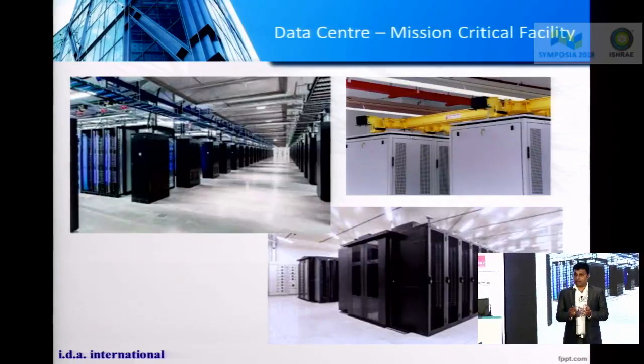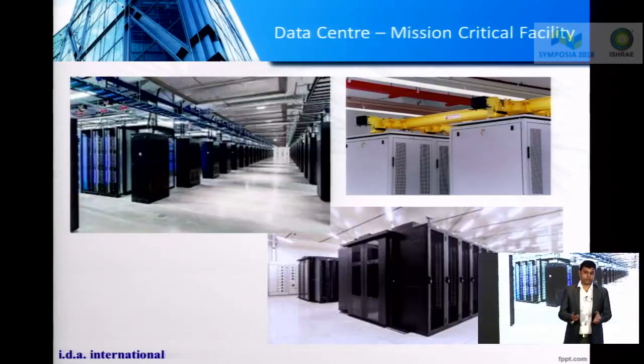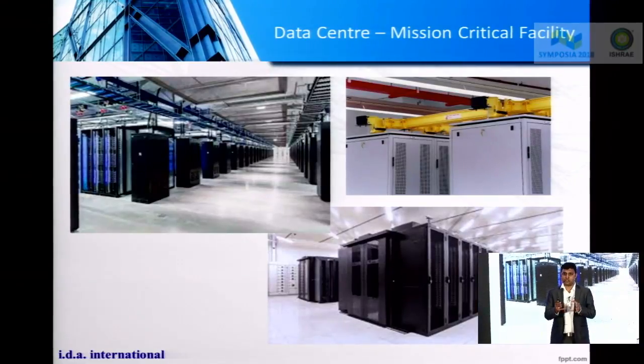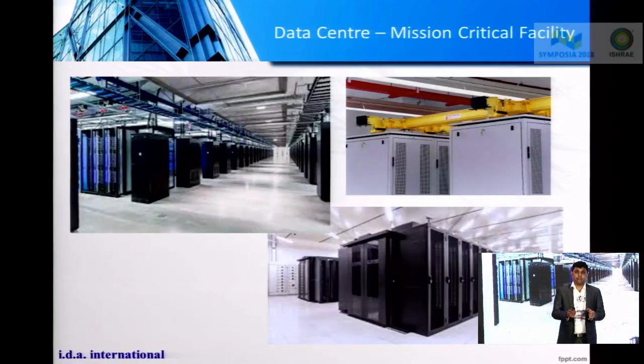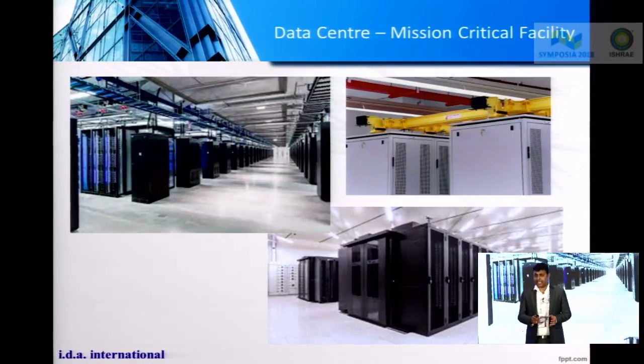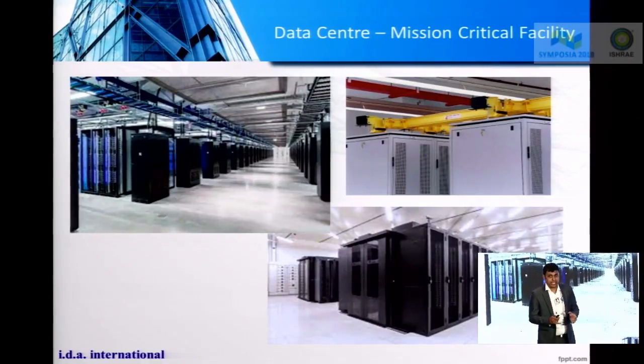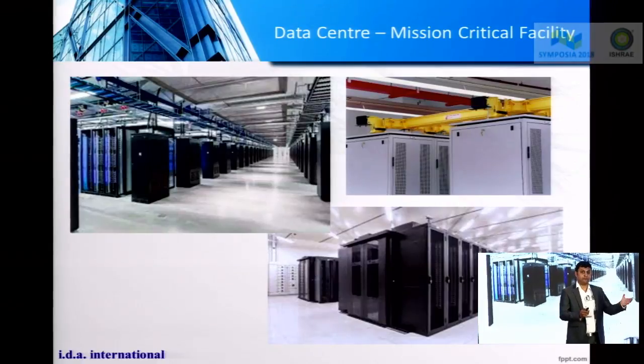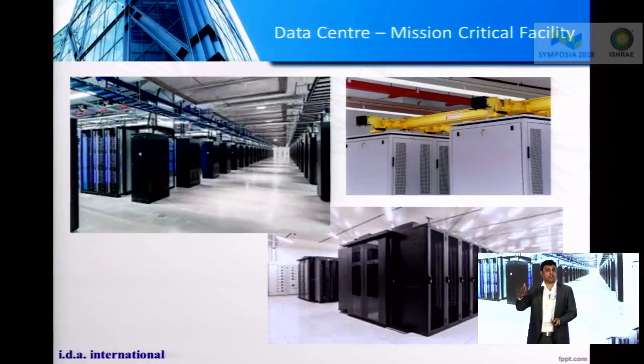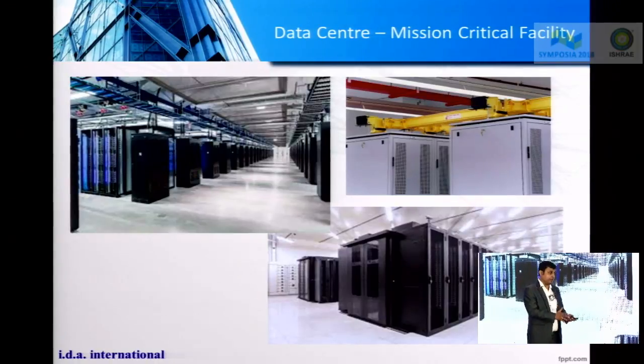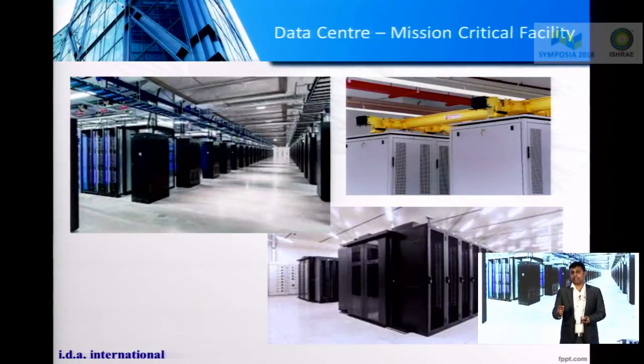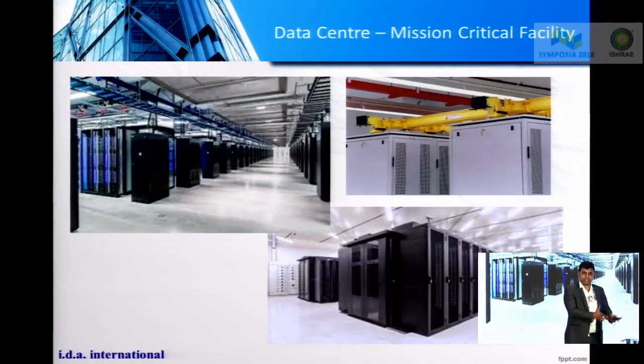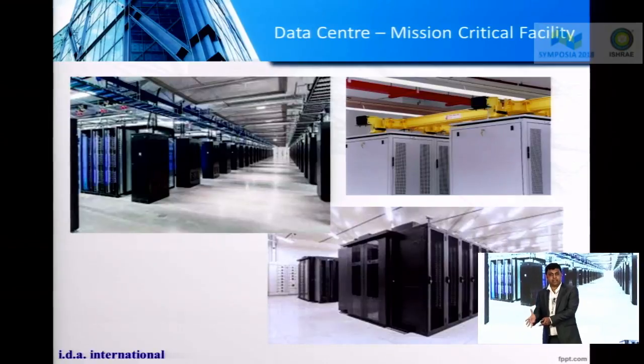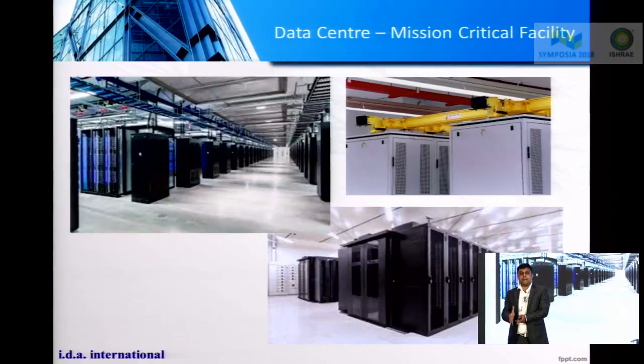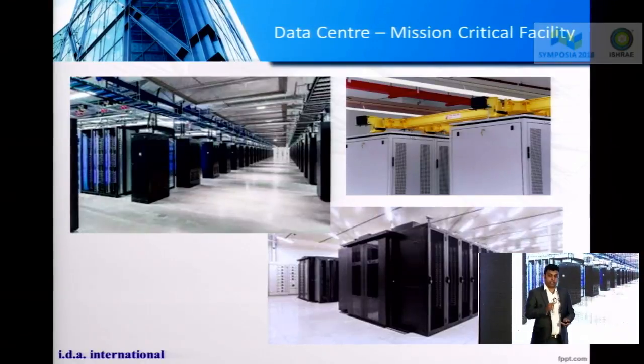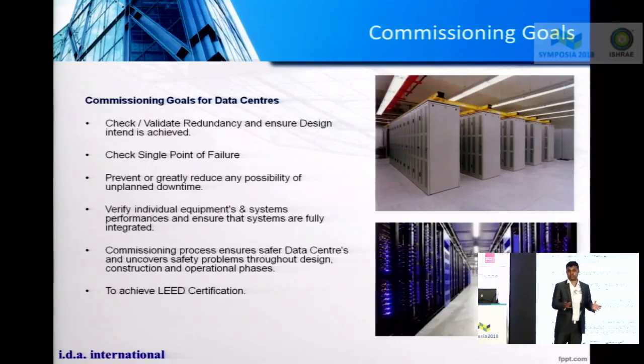Data center. There are many presenters who have told the importance of data centers, but we all know that a data center is a mission critical facility, which means a single failure could result in heavy economic losses. That's one of the reasons why many design consultants design data centers with tier 3 and tier 4, which means they're trying to add multiple layers of redundancy, which is pretty good. However, there's one thing that ensures that whatever you design is correctly implemented, correctly validated, correctly documented, operated, and maintained, and that's commissioning. So commissioning ensures that it meets the design intent or the design cause and effect.